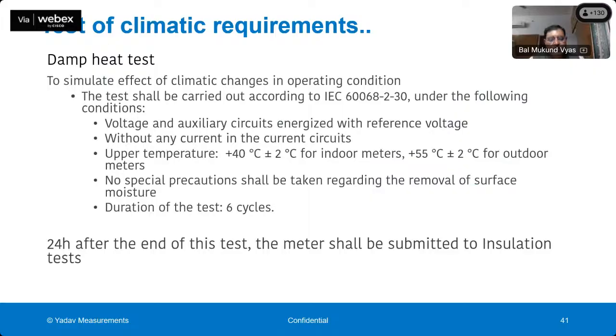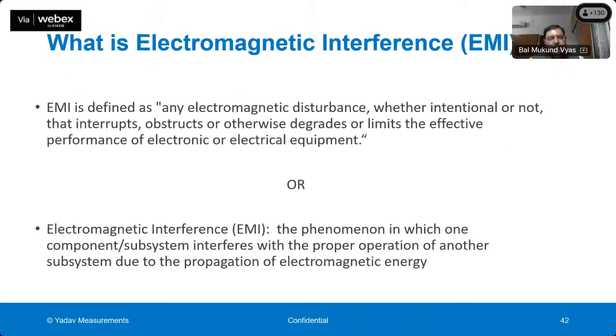After the test and after the 6 days are completed, 24 hours after that, the meter is subjected to an insulation test, and of course the meter's accuracy and functionality should not get affected.